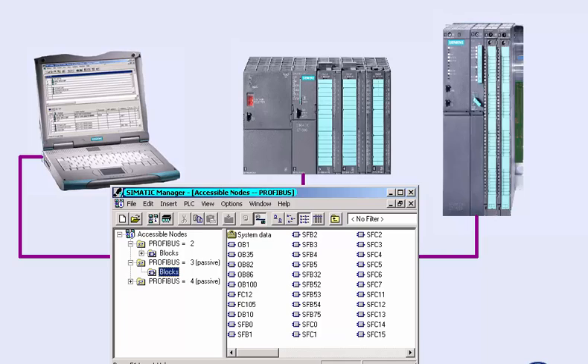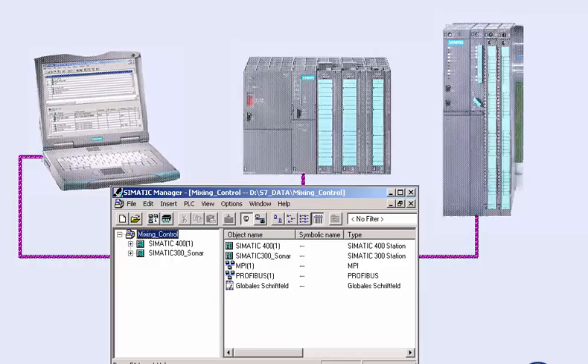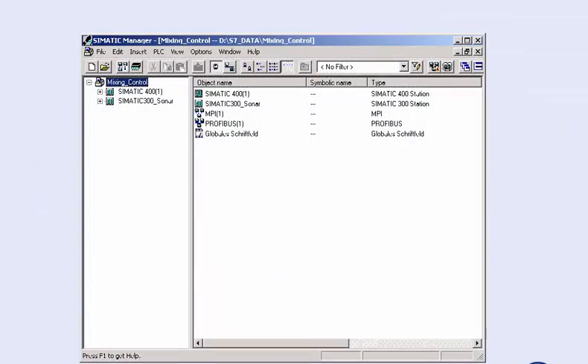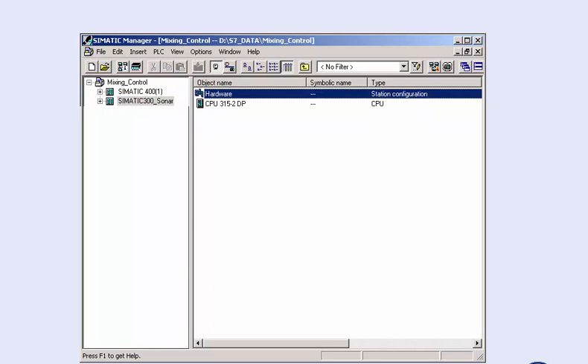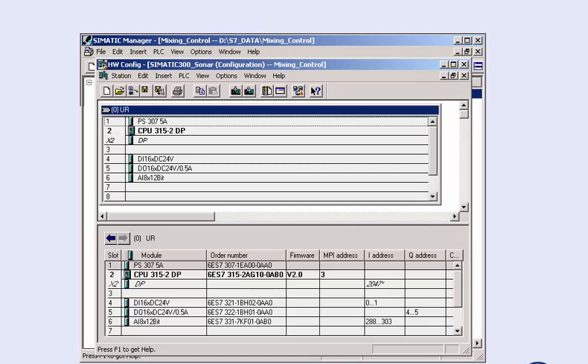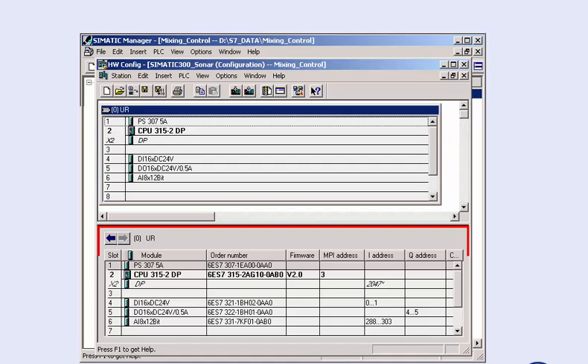This gives you a quick overview of which bus stations are already accessible with the programming device, allowing you to easily trace a faulty station configuration and correct it. For loading the given hardware parameters and configurations into the CPU, we open our project in the SIMATIC manager, select the station and open the configuration by clicking the hardware icon. The editor of the hardware configuration shows the rack with the modules in the upper window and the detailed information of the modules used in the lower window.